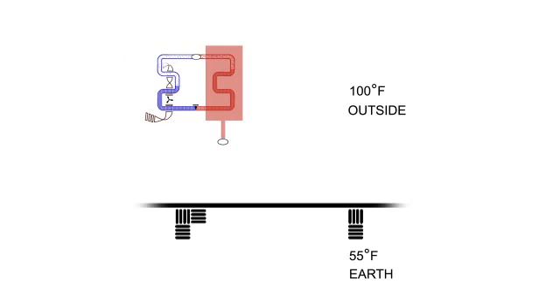In the summertime condition, the compressor reverses direction and the inside coil cools the recirculated air. Now we are in the opposite predicament with the same energy-intensive result. The outside coil doesn't want to condense in 100-degree heat. It wants to evaporate. It's hot.